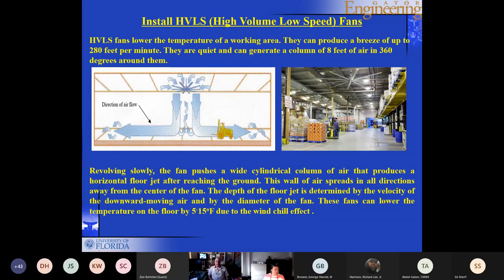Now, the next one is installing what we call HVLS fans, which are the high-volume, low-speed fans. And this is a picture of what they look like on the left side, and the right picture showed you one in one of the actual facilities that we've audited. These are revolving fans. They revolve slowly. The fan pushes a wide cylindrical column of air that produces a horizontal floor jet after reaching the ground. So you've got this big, huge horizontal floor jet. This wall of air spreads in all directions, a 360-degree direction, away from the center of the fan.